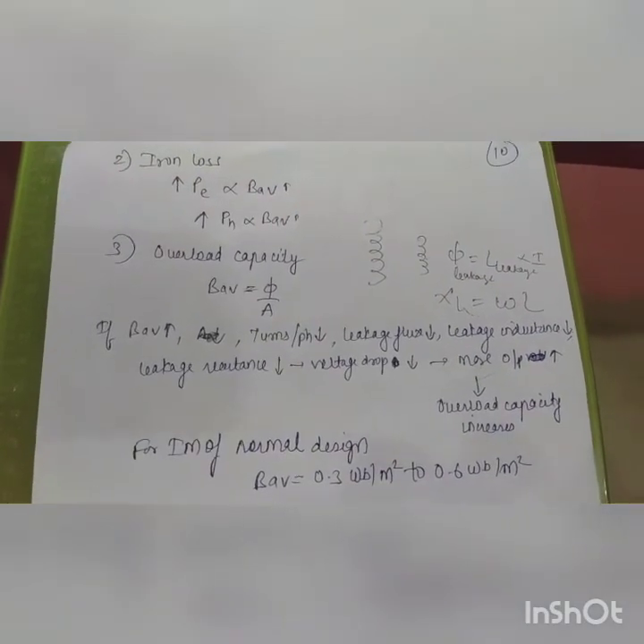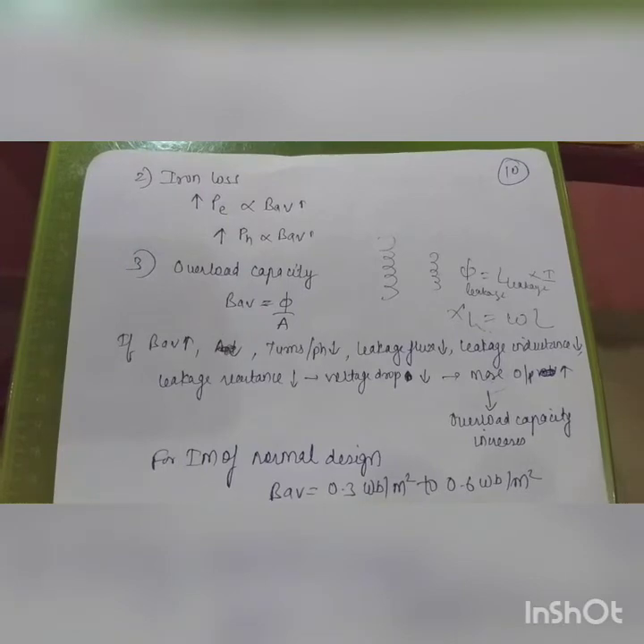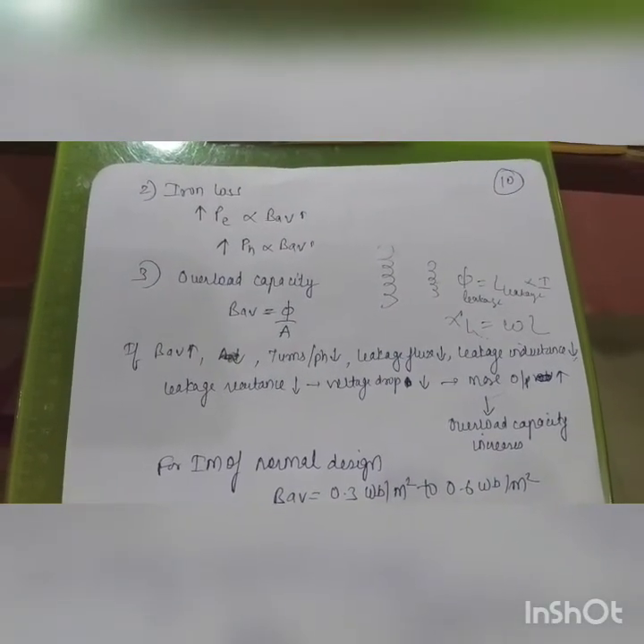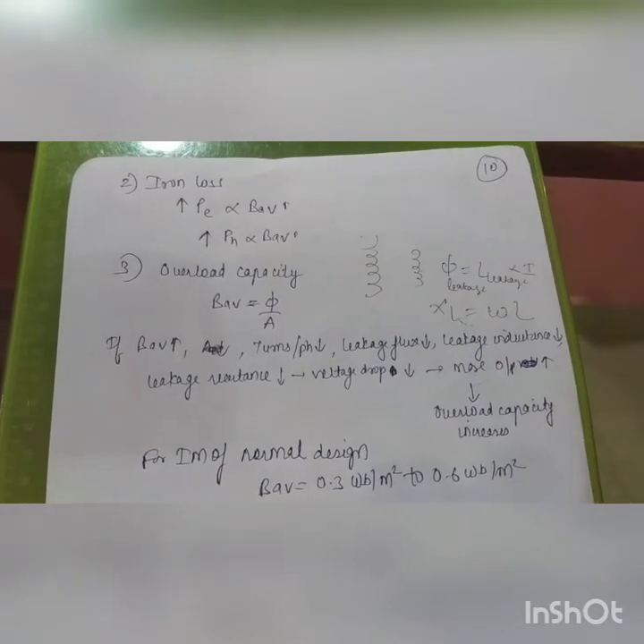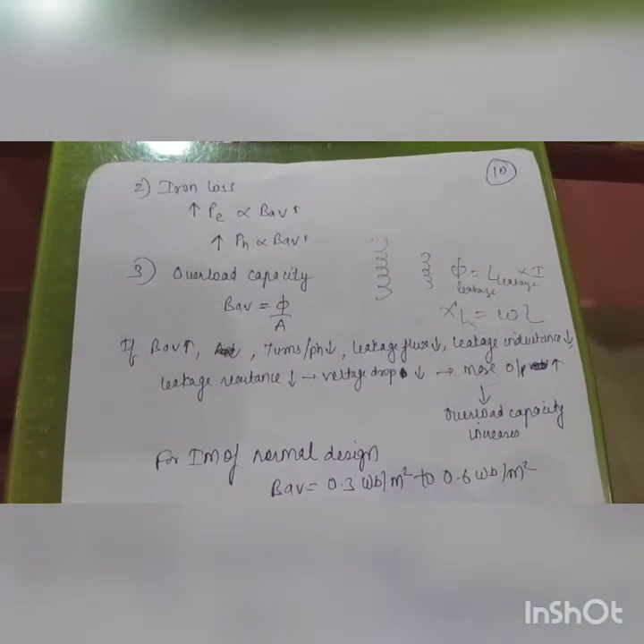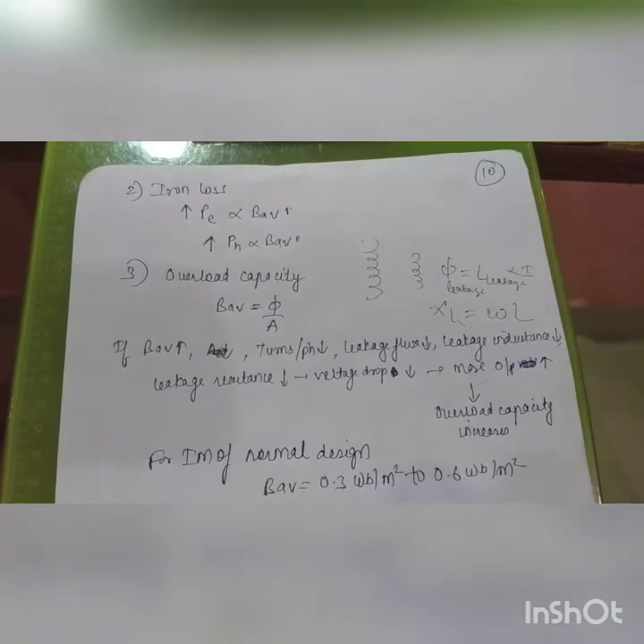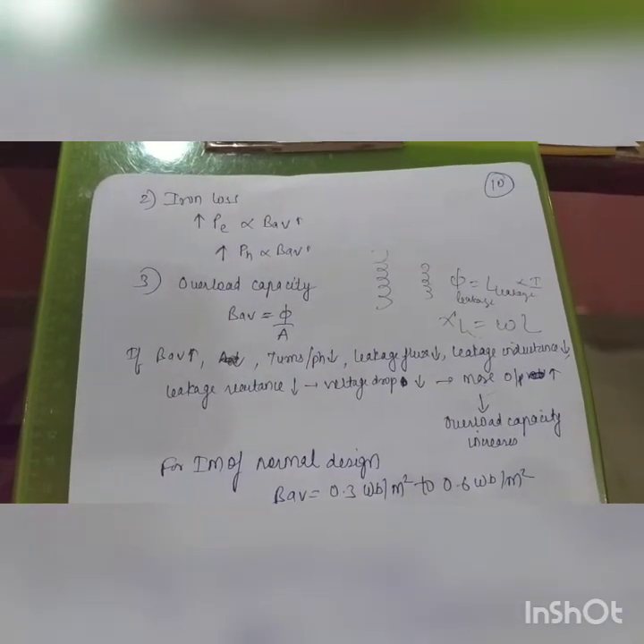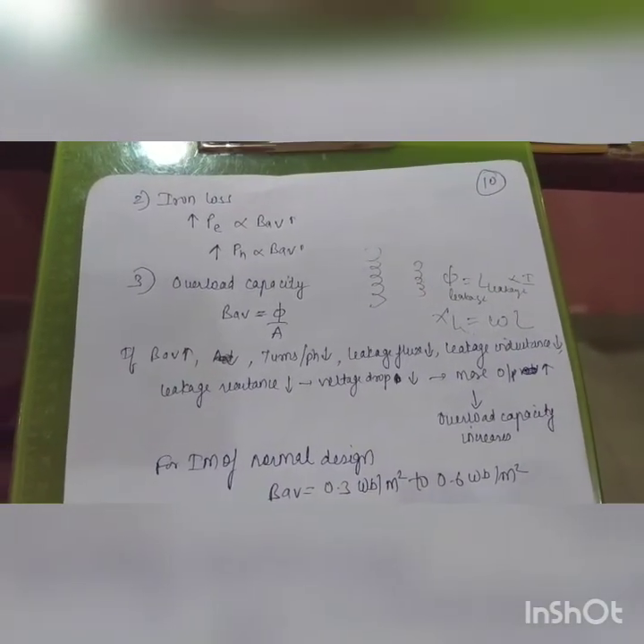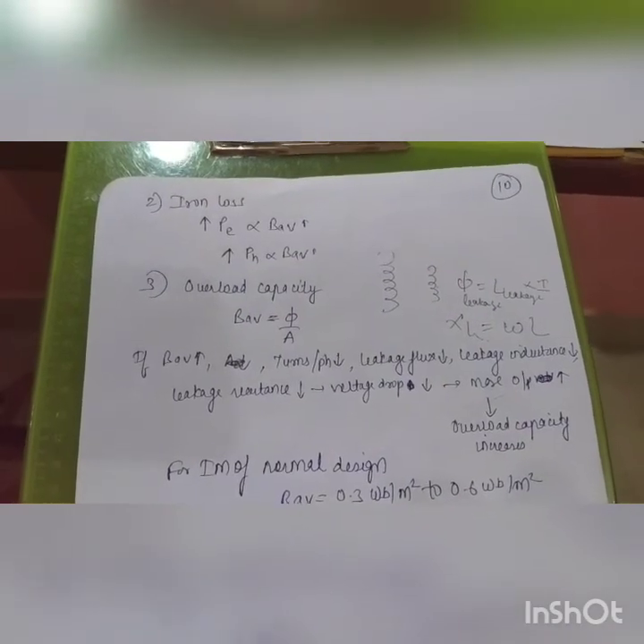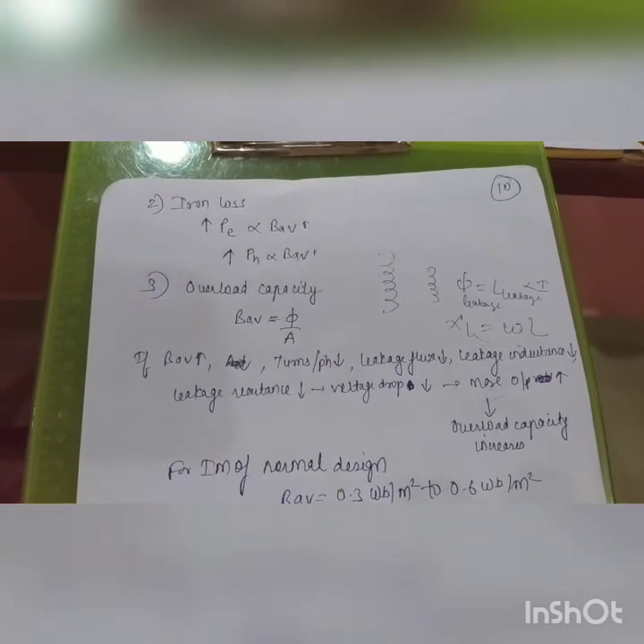So with high flux density there are two disadvantages: reduced power factor and increased temperature rise due to higher iron losses. However, there is one advantage: the overload capacity of the induction motor increases. The typical range of Bav is 0.3 to 0.6 Wb/m². If the thermal limit is exceeded, the insulation will be damaged first, hot spots will form, windings will short, and the induction motor will be damaged.